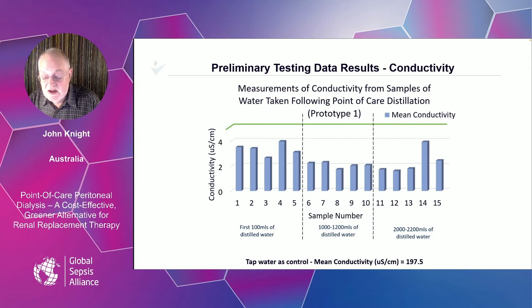We measure fluid sterility in 3 different ways. Firstly, conductivity, by passing an electrical current through the fluid. Tap water has a conductivity of around 200 microsiemens per centimetre. The British Pharmacopoeia standard for WFI is less than 5, shown here as the green horizontal line. This graph shows 15 water samples measured in triplicate: 5 taken early in the 2.2 litre bag fill, 5 more in the middle, and 5 more at the end, and they are all well below the target.